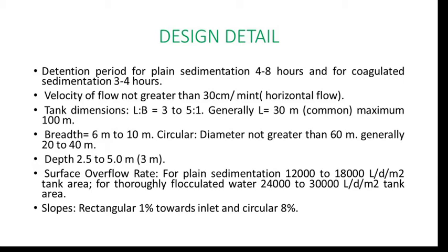And if you are considering the coagulation process and coagulated sedimentation, they require a minimum detention period of 3 to 4 hours. So for plain sedimentation it is 4 to 8 hours, and for the coagulation process it is 3 to 4 hours. How do we calculate the detention period? The detention period or detention time can be calculated as the volume of the tank V divided by the rate of discharge Q. So detention time T = V/Q.